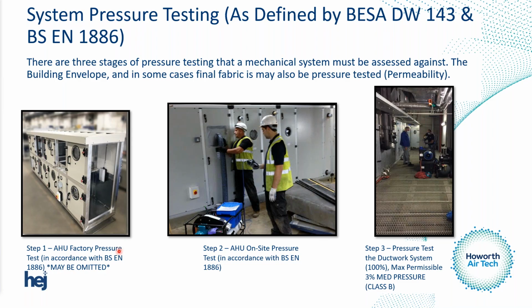And this step has been omitted by the authorising engineer for Vent, because he's basically said, what's the point in doing that in a factory, then breaking it up and swinging it onto site through a crane and then redoing the pressure test again? So we could sometimes skip that, but it has to be a discussion with the authorising engineer for Vent on behalf of the customer. Step 2, we get to site, and it's absolutely essential that the AHU is then pressure tested on site. Your manufacturers, AHS or Mansfield Pollard or whoever it may be, would offer that service or could potentially offer that service.